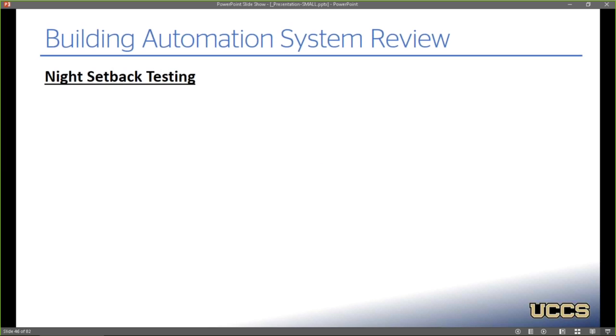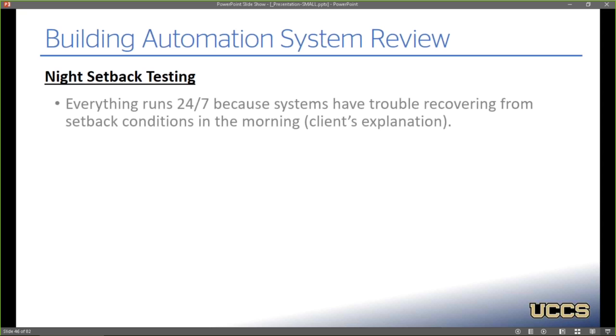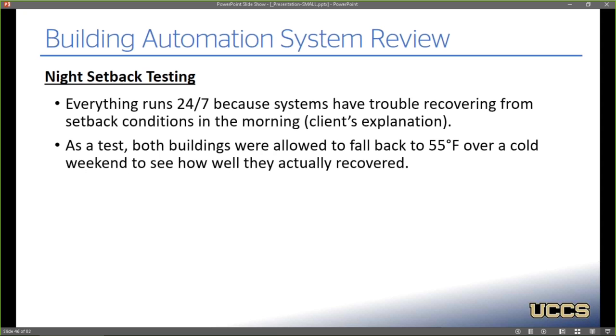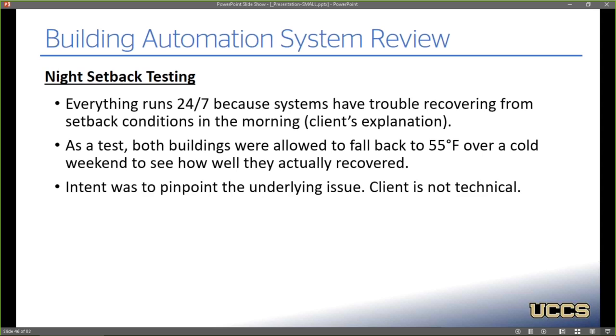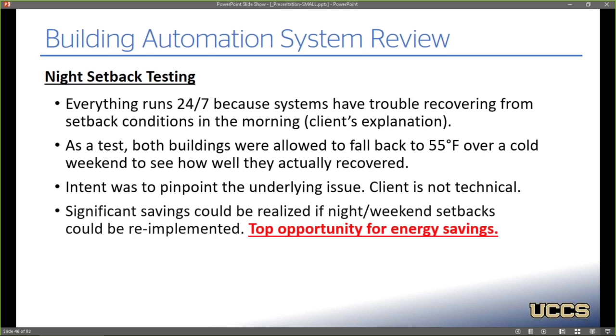So as I mentioned, everything's operating 24/7 because they said they can't recover from night setback. Well, the customer here is not very technical, and they can't tell us why. They just know it doesn't work. So as a test, over a weekend we allowed the spaces to fall back to 55 degrees, just to watch the following morning and see what happened, and hopefully find the smoking gun that the customer doesn't know about. And if we can figure out what that is, then we can re-implement the HVAC scheduling and temperature setbacks. That's our top opportunity for energy savings.